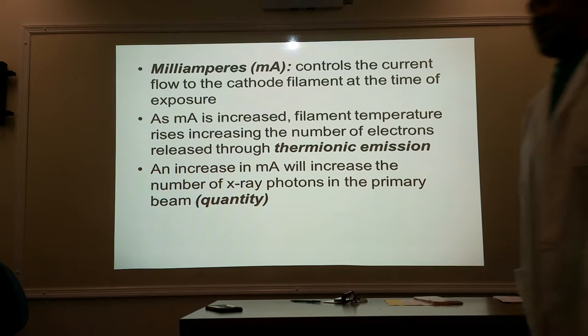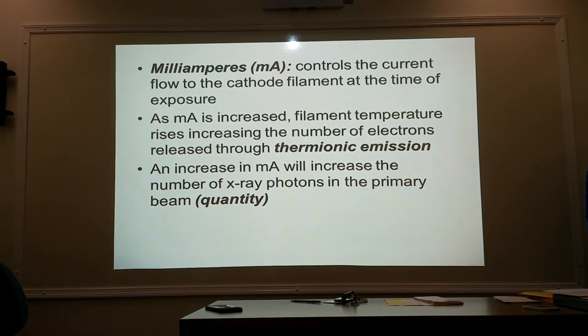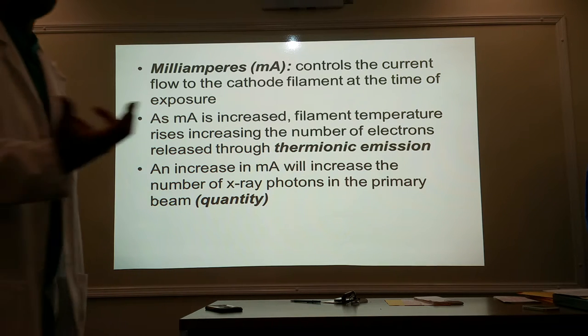Let's talk about MA. Milliamperage controls the current flow to the cathode filament at the time of exposure. With higher MAs, we're controlling the amount of electrons — the amount of electrons being boiled off from the filament through the process known as thermionic emission. The higher the MA, the hotter the filament gets, the more electrons are boiled off. We're controlling quantity, not quality — the number of electrons being boiled off.